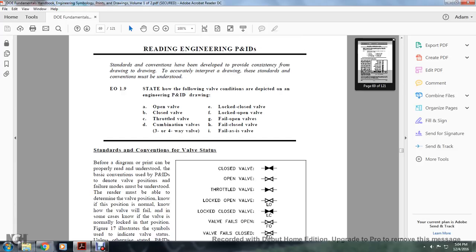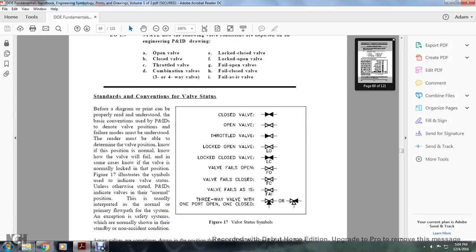Reading Engineering Piping Instrument Designs: standard conventions have been developed to provide consistency from drawing to drawing. These standards must be understood. The following valve conditions are depicted on engineering piping instrument drawings: open valve, closed valve, throttle valve, combination valve, three or four-way valve, locked closed valve, locked open valve, fail open valve, fail closed valve, fail-as-is valve. Figure 17 shows these valve status symbols. Before a diagram can be properly read and understood, the basic convention of the piping instrument drawing to denote valve position and failure modes must be understood. The reader must be able to determine the valve position normally, whether the valve is in fail condition, and whether the valve is normally locked in position.